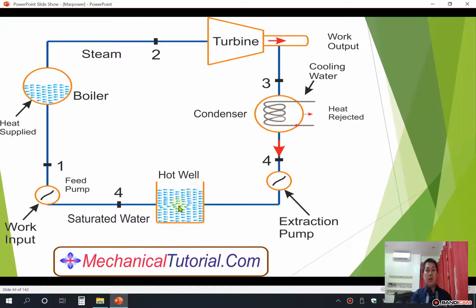First, your feed water is located here in the hot well or cascade tank. It will be sucked by the feed pump and delivered to the boiler, and there is heat supplied here from your burner. Then it will boil and generate steam. The steam will flow to your turbine. The turbine will run, and this turbine is connected to a generator, so it will create electricity. After the steam is used in the turbine, it will flow to your condenser. Then there is heat rejected here. Your steam temperature will be absorbed by the cooling water, and this steam will become condensate again, and the extraction pump will take suction and deliver it to the hot well. This is the basic steam cycle.